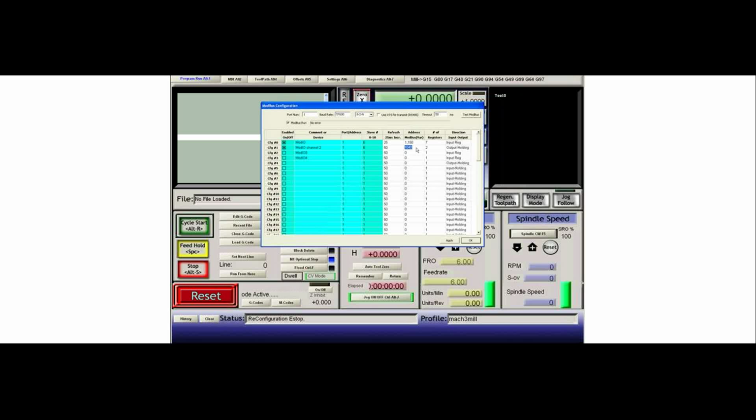My Mod I/O is currently running at the moment and is every 25 milliseconds transferring in the first 7 registers of the Mod I/O, and every 50 milliseconds it is sending 2 registers out to the Mod I/O. And these are going into configuration 0 and 1. 0 is receiving data. Configuration 1 right now is set up to send data. As I said, you can set up to 63 of these configurations, and thus you can send whatever memory words you want at whatever timing intervals you want back and forth from any PLC. This is serial only, take note.